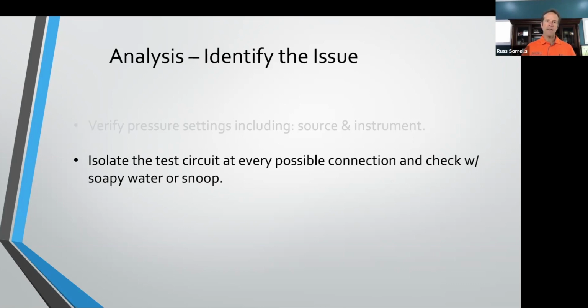So when I say every possible connection, you've got a hose or an air line that's coming out of the instrument going to your fixture. Well, I would separate that, where that line goes to your fixture, and just plug that off. Find a way to cap that and just test that. So just run a test to see, is there significant pressure loss out of that section of hose? If there is, then obviously that could be the issue.